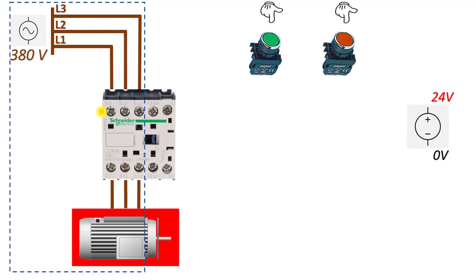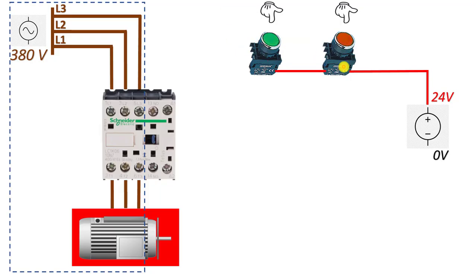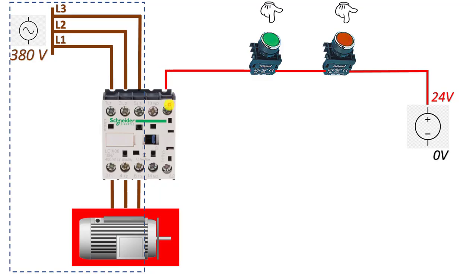For the control circuit, I exit the 24-volt power supply from the plus side and enter the stop button. I jump from the stop button to the start button, then exit the start button and connect to the A1 coil leg of the contactor to send the necessary trigger. I enter the A1 coil leg. My 24-volt connection from the plus side of the power supply to A1 is now made.